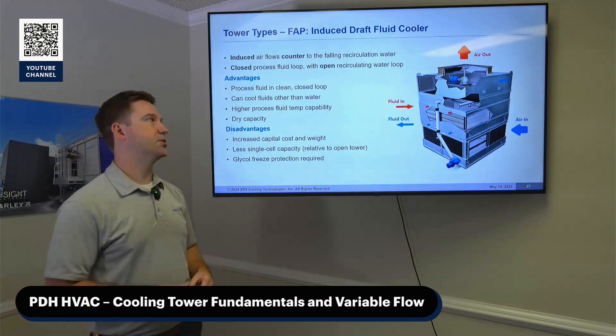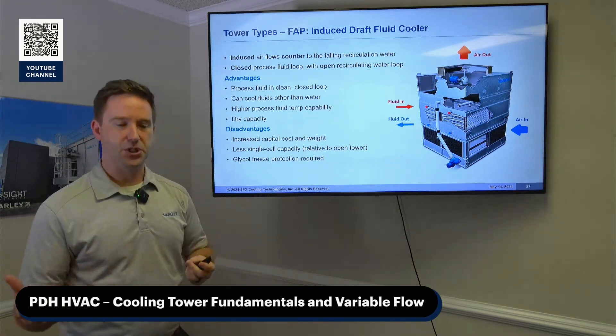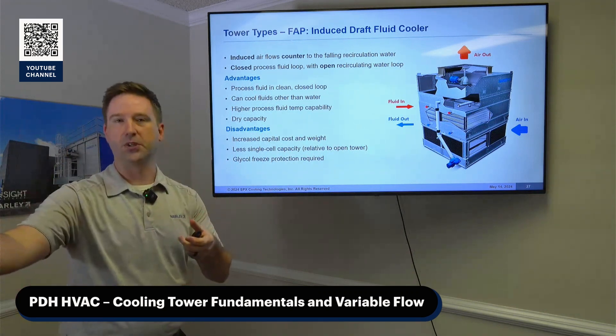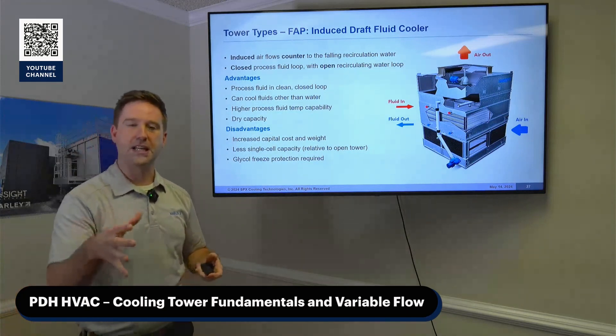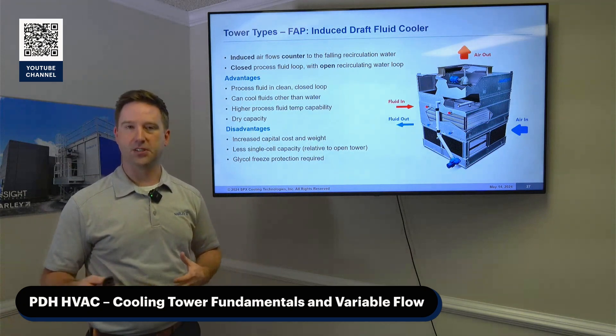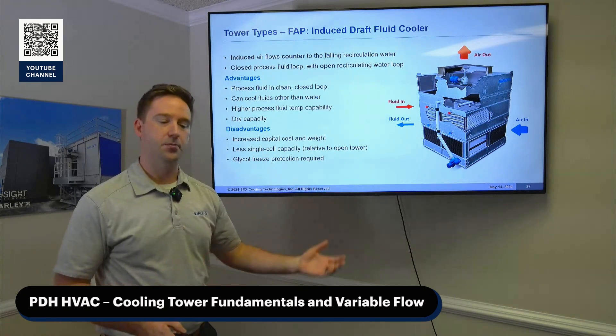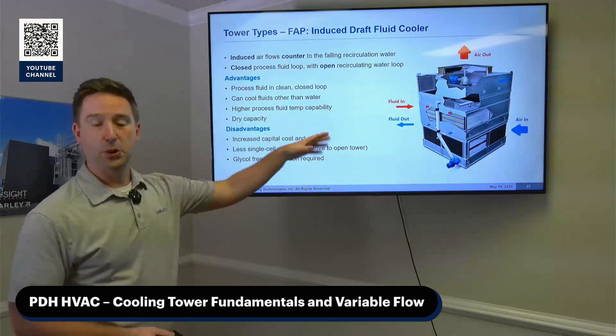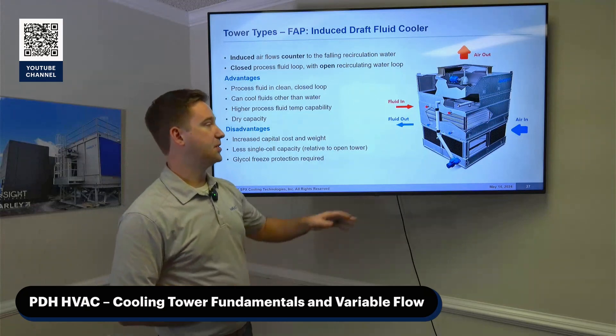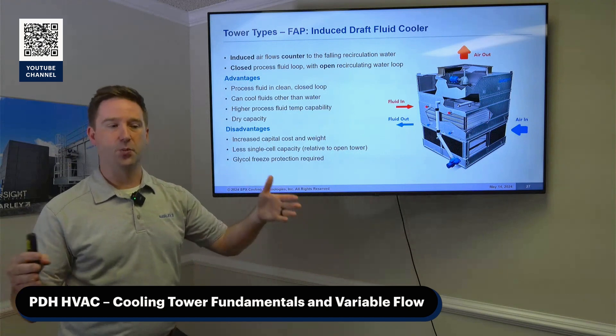Another type is the induced draft fluid cooler. On typical open cooling towers, if you're using a chiller, water from the tower might hit a plate-and-frame heat exchanger before going to the chiller to keep that water clean. But in a heat pump situation — like at a university, nursing home, hospital, or hotel — a fluid cooler is a good option. A fluid cooler takes your process fluid and runs it through coils internal to the tower, essentially combining a plate-and-frame heat exchanger and an open tower into one.